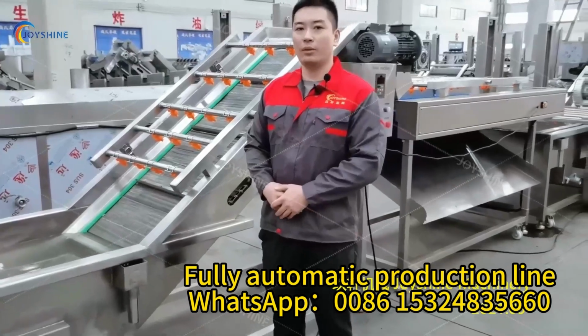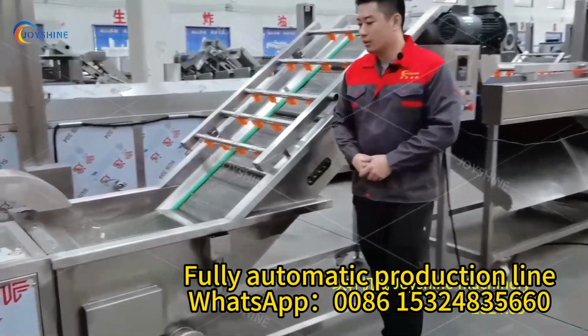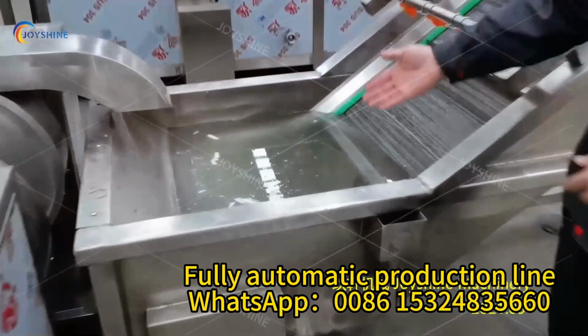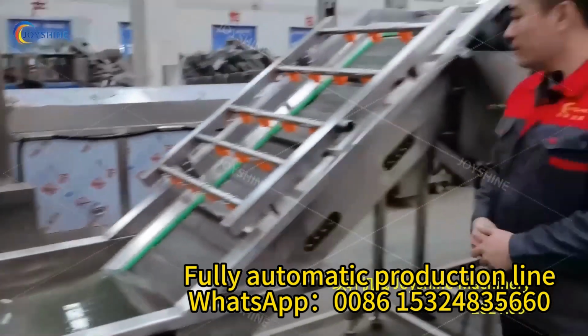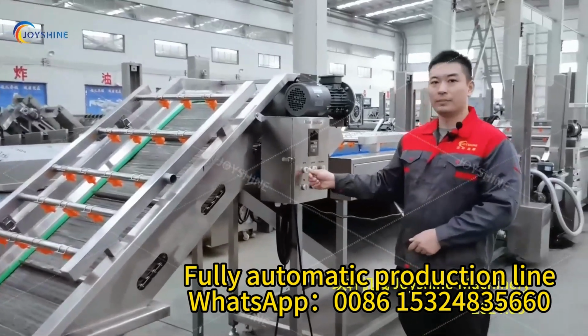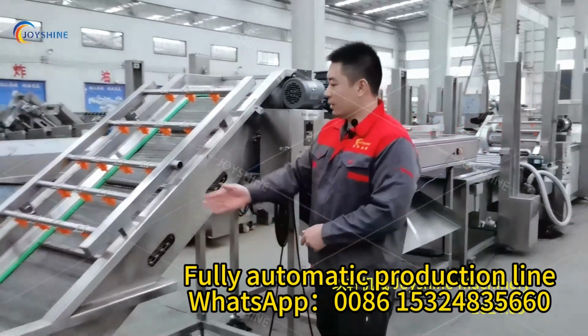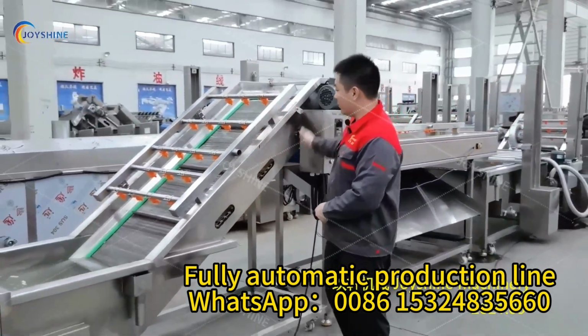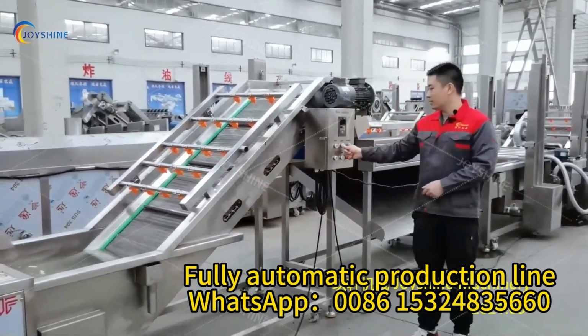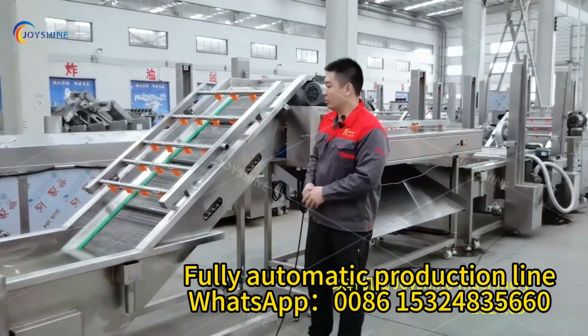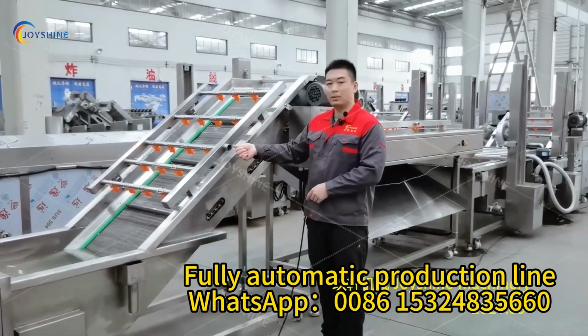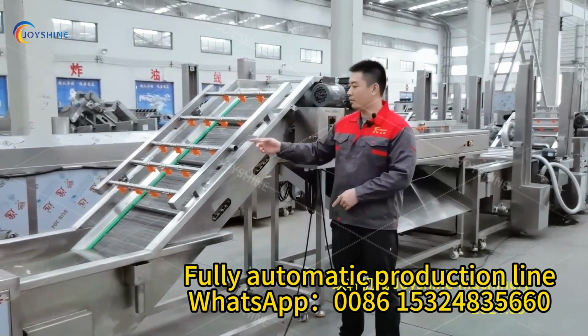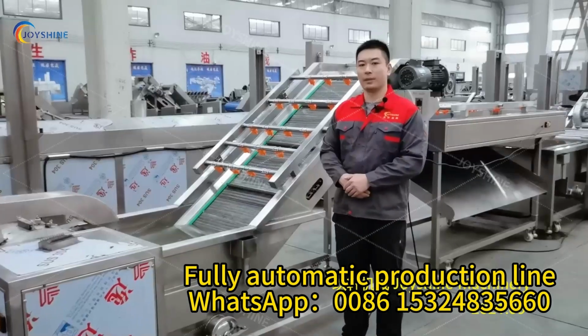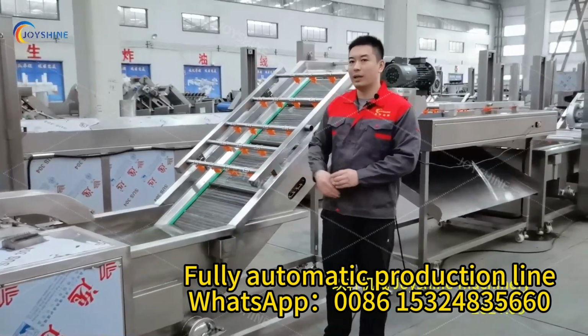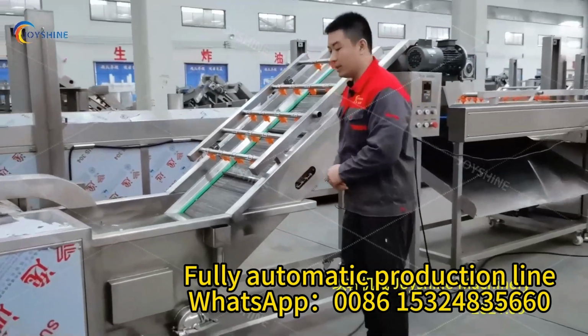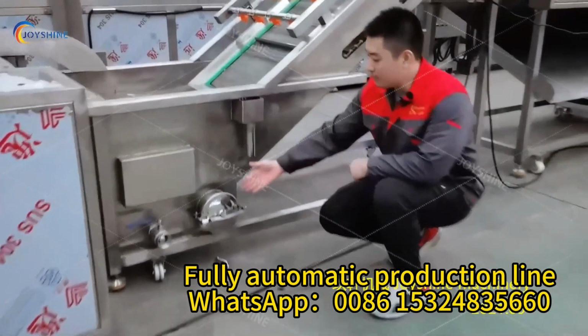Now I will show you how to operate this machine. First, you need to fill clean water into this tank and then press the start button. And you can adjust the operating speed of the belt by pressing these buttons. Please remember, do not open the water supply for this pipe during the operation. It is only for cleaning purposes. You need to change the water every 8 hours, and you can clean up the waste from this port.